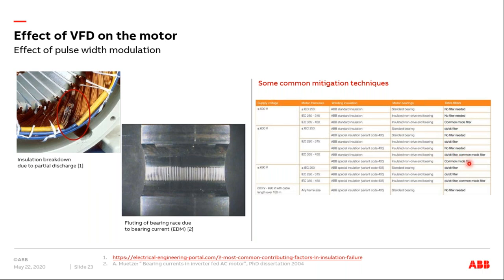And then for the bearing current, we are trying to use insulated bearings in some of our products, and we also use ceramic bearings if the customer really requires it. There are also ways to ground the shaft. So I would say there are different ways of mitigating. What I wanted to highlight is that there are more benefits to using a VFD than drawbacks. The drawbacks are a well-known issue, and they can be mitigated using different methods based on the customer's requirement.